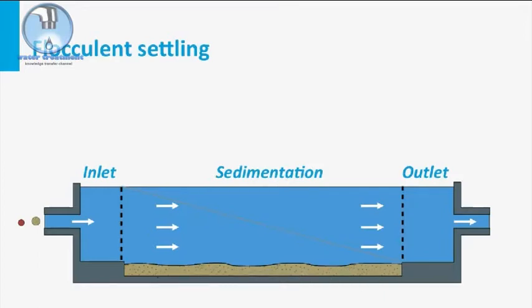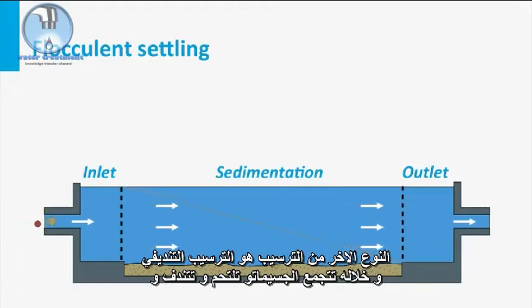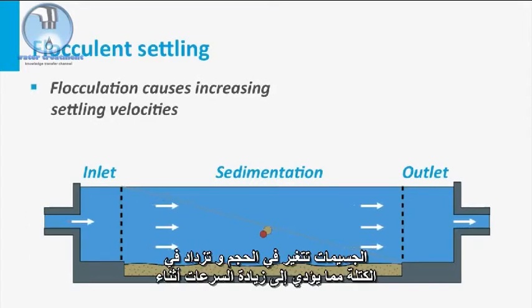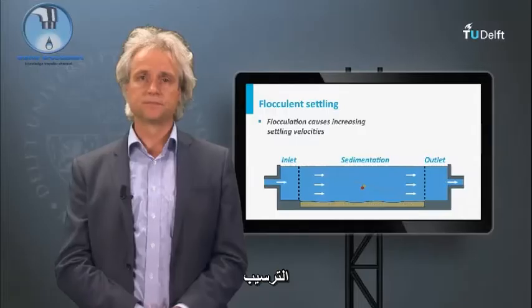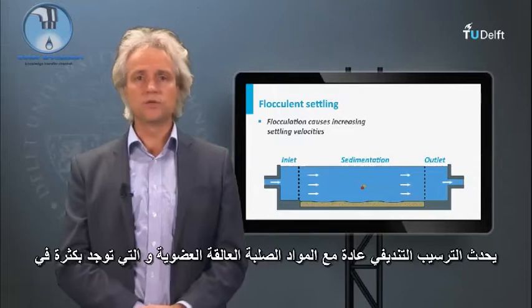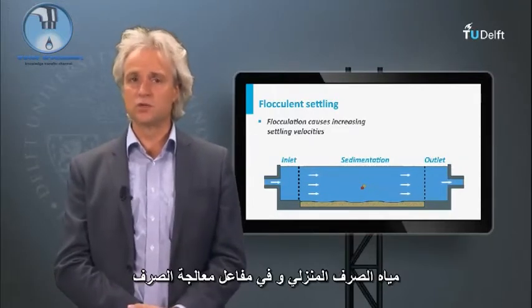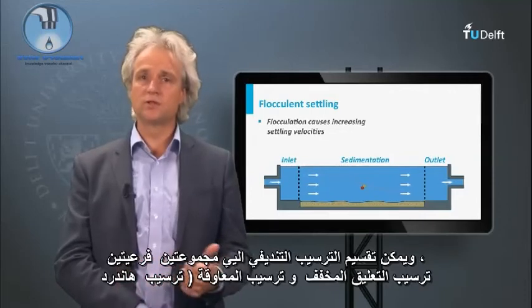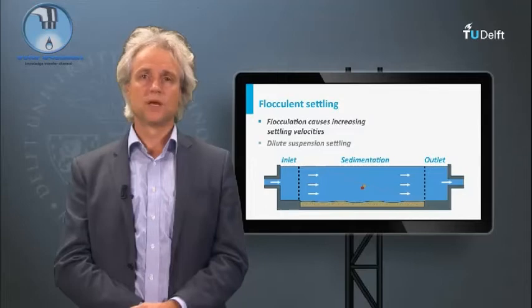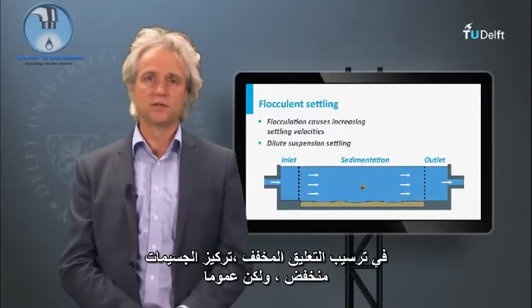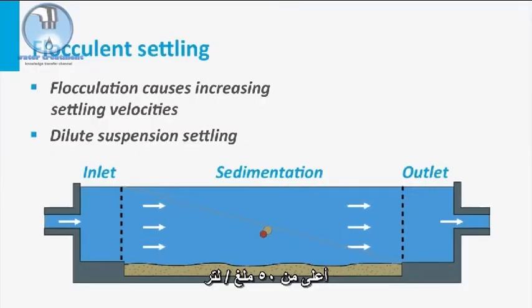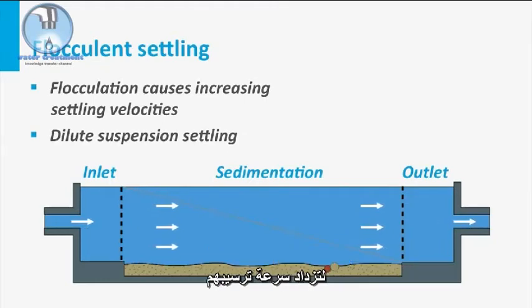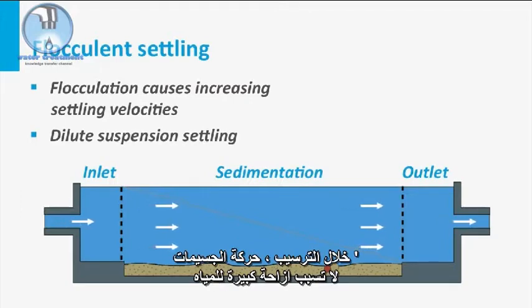The other type of settling is flocculent settling. During flocculent settling, particles agglomerate, or coalesce, or flocculate, and have no constant characteristics. The particles vary in size and increase in mass, resulting in increased velocities during settling. Flocculent settling generally occurs with organic suspended solids, which are largely present in domestic sewage and downstream sewage treatment reactors. Flocculent settling can be divided into two subgroups: dilute suspension settling and hindered settling. In dilute suspension settling, particles are present in low concentrations, but generally higher than 50 mg per liter. Particles are free to coalesce with any other particle during sedimentation, and their motion does not cause significant water displacement.